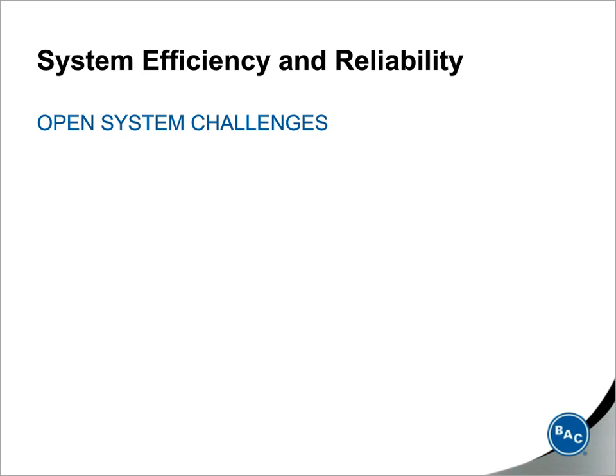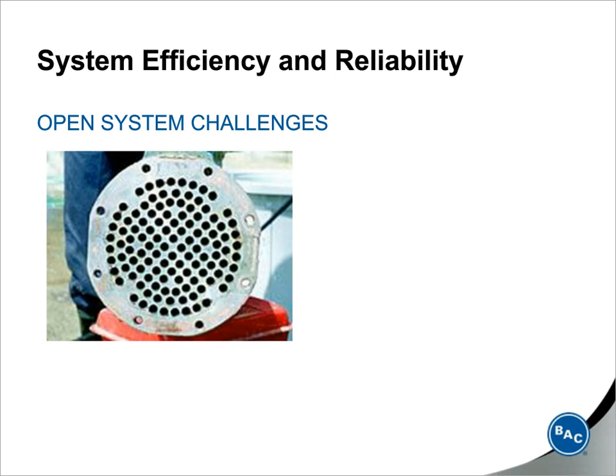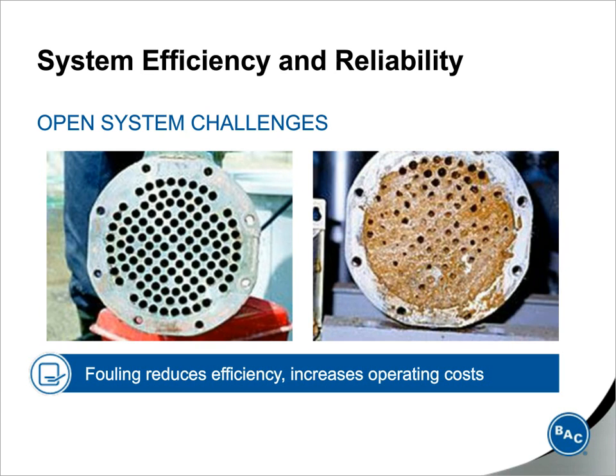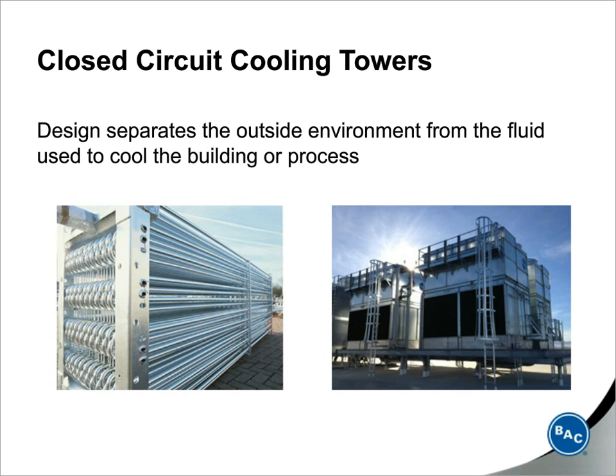To put this in perspective, or to really highlight the magnitude of fouling and what it can do, this is a picture of a typical heat exchanger before system operation. Now, without cleaning the tubes, you can see what happens over time. This is the fouling that can occur, and it can really reduce your chiller or your system efficiency. So the question is, what can we do about it? As I mentioned earlier, we can close the condenser loop with a closed-circuit cooling tower.